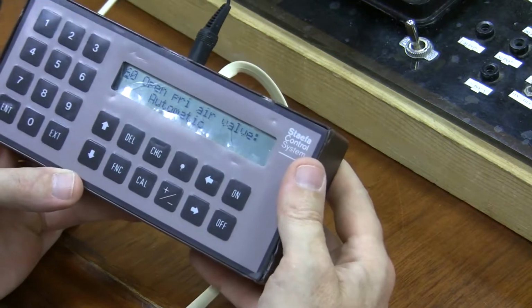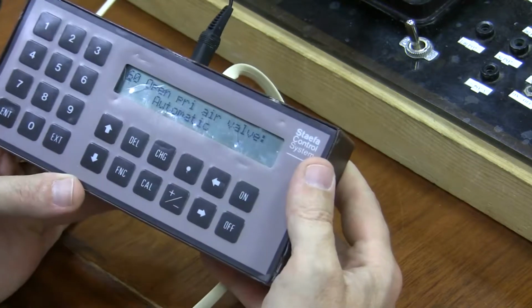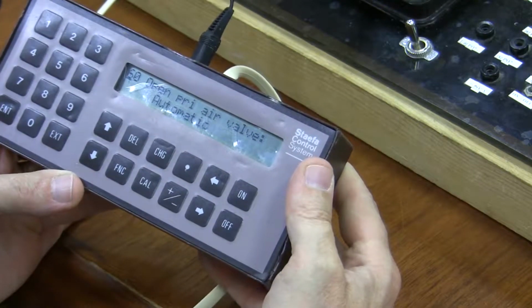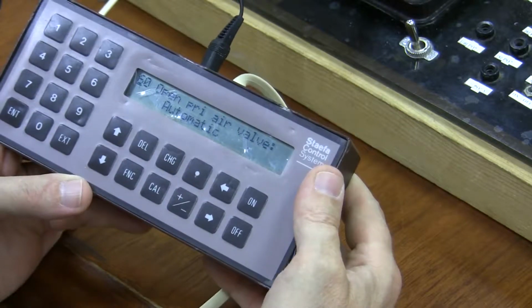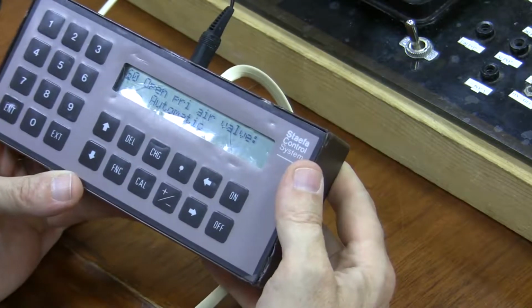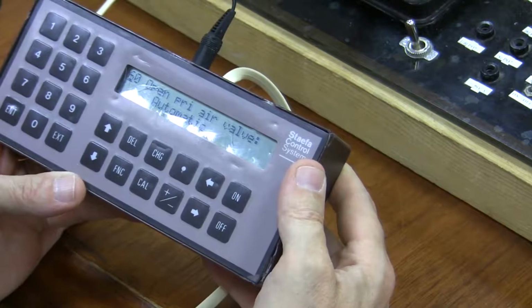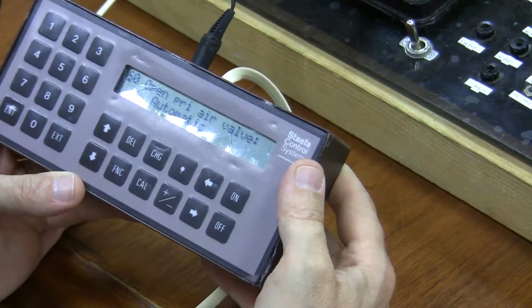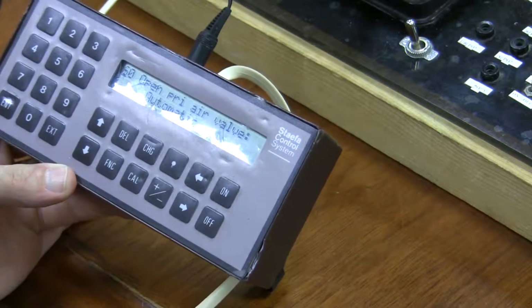And the reason we can't change something is because we're not in the correct mode. We're in a read-only mode when we connected. So we've got to change ourselves to what they call a commissioning mode, which allows us to actually make changes. I still see all the same parameters, I'm just in a commissioning mode, and it'll allow us to do that.